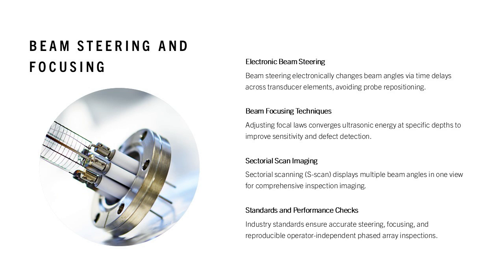Electronic steering simplifies coverage of weld bevels and complex geometries, while sectorial scanning, S-scan, displays multiple angles in a single view for comprehensive imaging. According to ASTM E2700-20, S-scans produce a swept-angle visualization that increases defect detection probability and coverage. ASME guidance further reinforces that encoded electronic scans improve reproducibility and allow for consistent operator-independent data acquisition. ISO 18563-1 specifies performance checks to ensure phased array instruments accurately deliver focal laws, steering precision, and consistent pulsing characteristics essential for reliable inspection outcomes.